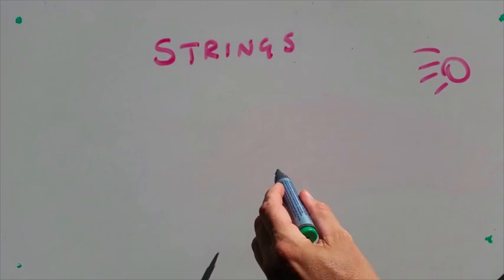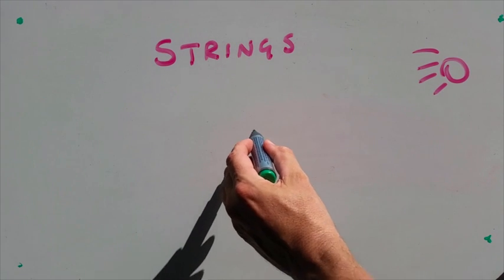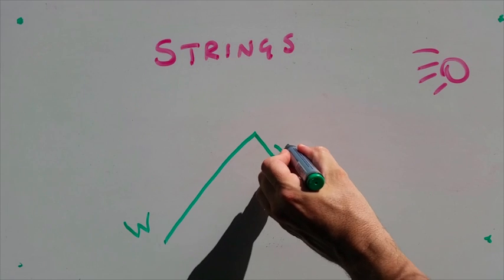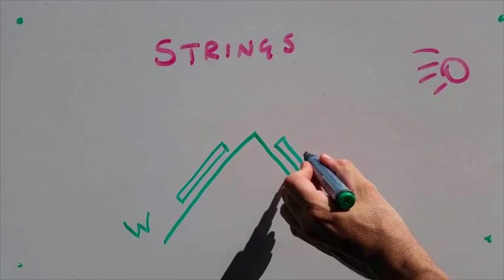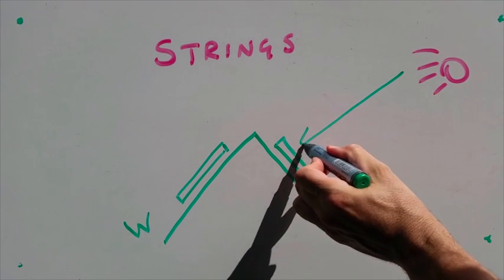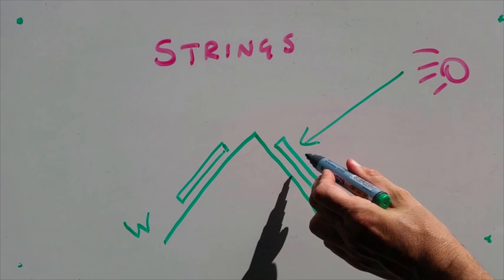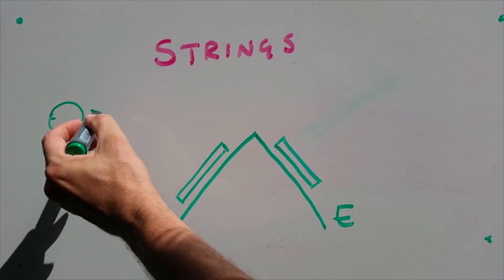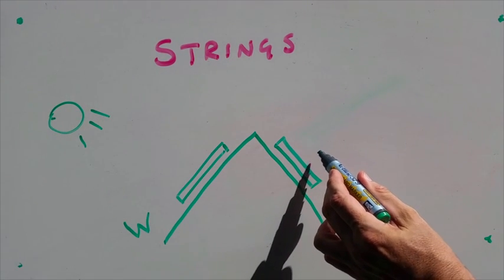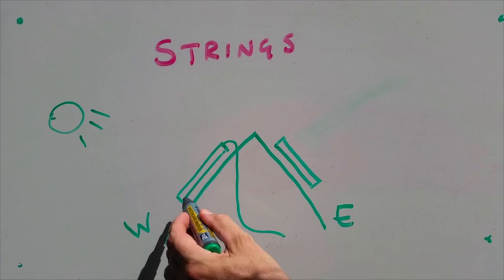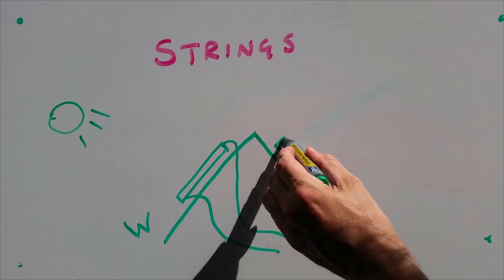Now sometimes people need more than one string. So if your roof is like that, so this side is facing east and this side is facing west. This is very exaggerated just to prove a concept. And you've got panels here and panels here. So these get morning sun and these get afternoon sun. So when these are being lit up, these are producing a lot of power, but these are producing very little. And so you get an imbalance.